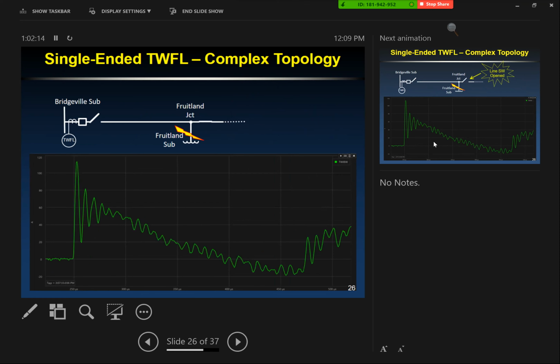Fortunately for this event, operators took further action and opened up this switch here by SCADA. So our operators from their office are able to open up the switch, test back into the line, make sure that the fault isn't on this section here. When they do that, energize the line. There we get our first impulse, line energization. Now when this arrives to Fruitland Junction, there is no junction point. This is going to continue right on down to the Fruitland sub without any reflection off the junction. And our first reflection is off the faults. So now we have a nice clean picture. This is the event you're going to be using to do your fault location, if you're lucky enough to have operators sectionalize your line and test.